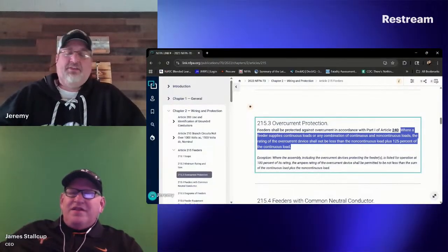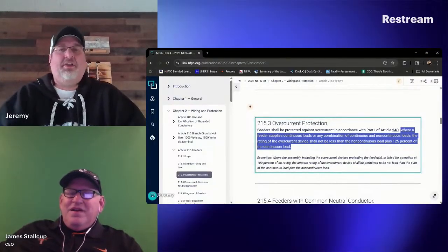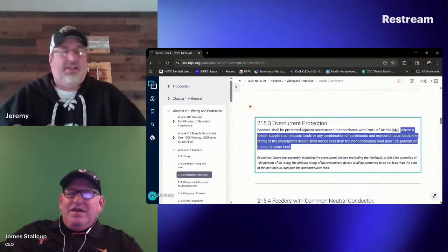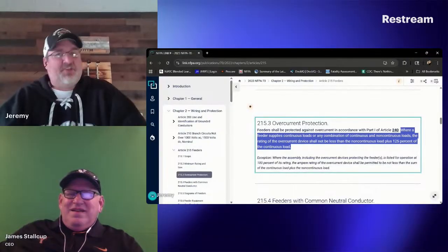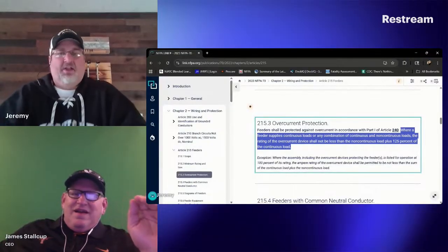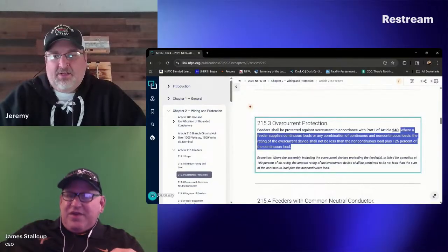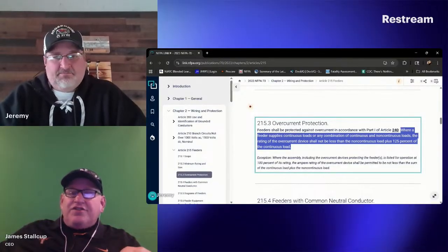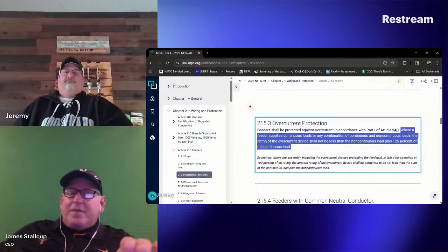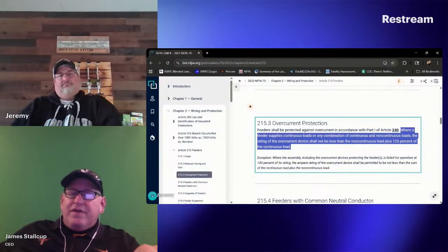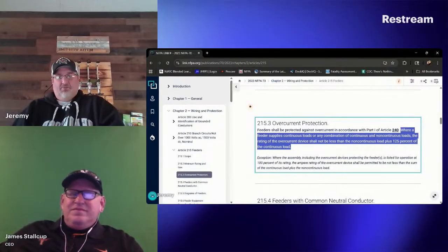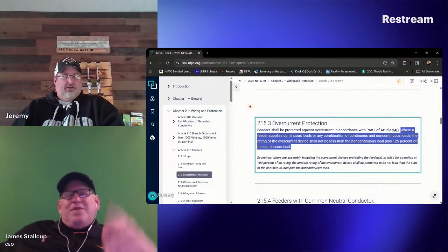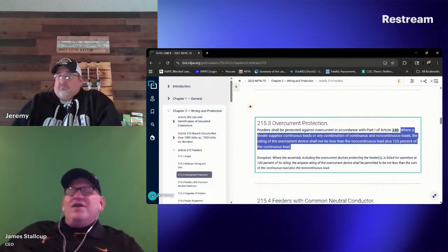No, I'm saying you have 920 amp wire, so you drop down to a 900. Again, why can't I drop down to an 800? Why can't I drop down to a 700? Where does it say you drop down to a number that ends in a zero? It says it right there. No, it does not. The conductors it protects shall be equal to or greater than the rating of the overcurrent device. So I go down. I agree. But where does it say you have to drop down to a 900? Why can't I drop down to an 875 or an 850? Well, just drop it down to a 50 amp. Drop it down to a 100 amp.